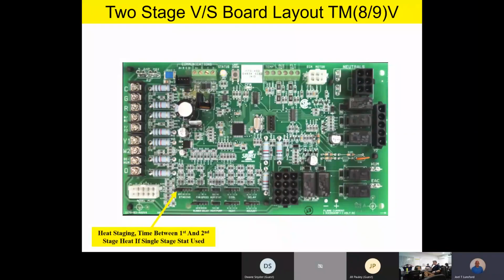Now, team, we always recommend you have a 2-stage heat, 2-stage cool thermostat on this product. That way you have the ultimate comfort. But if you are stuck with a single stage thermostat, we do give you some staging options, but make sure you've got it on something other than off. Because if it's on off, just remember, you'll never get out of single stage heating. Any questions or comments on the jumpers before we cover one more little point, and we'll take some questions after that? No, we're good. Everybody good? Okay.